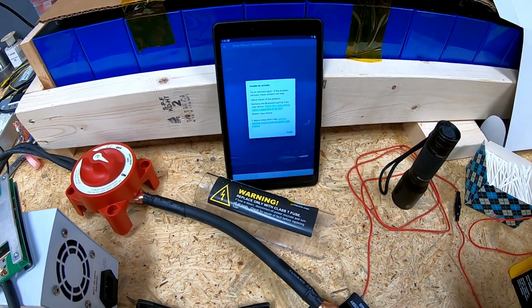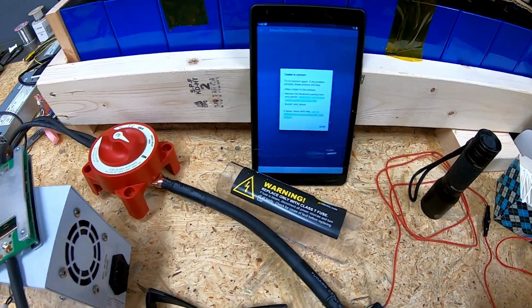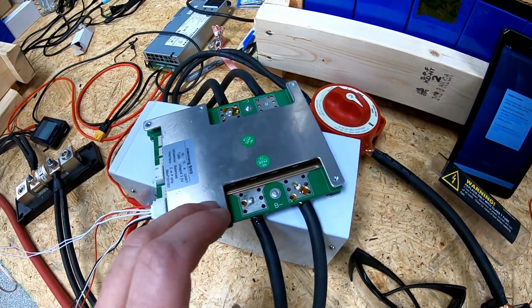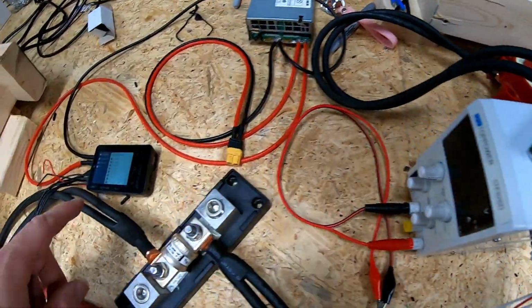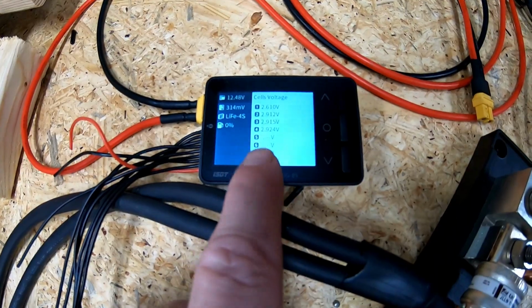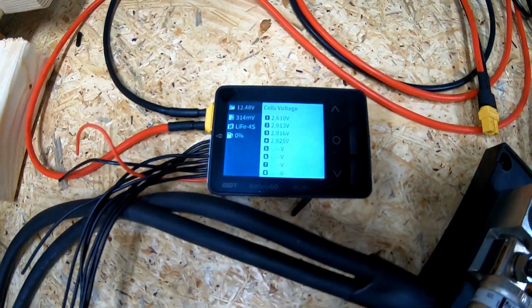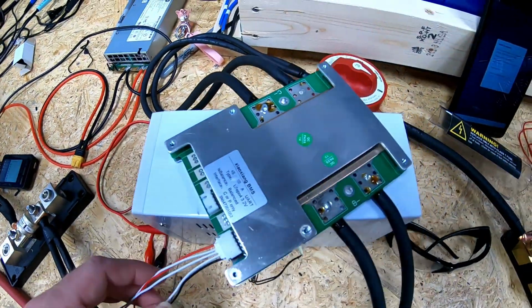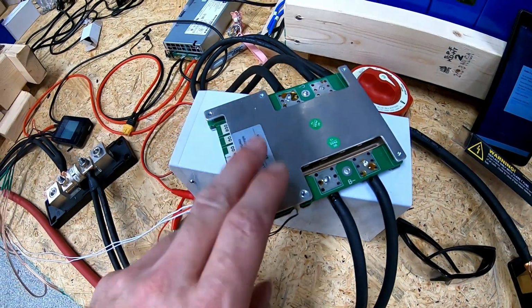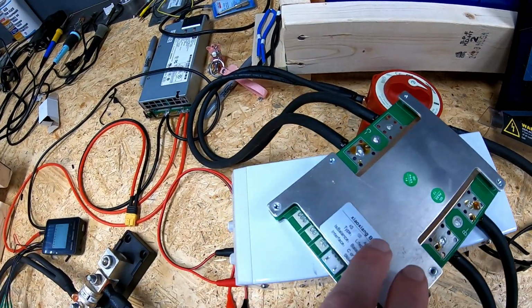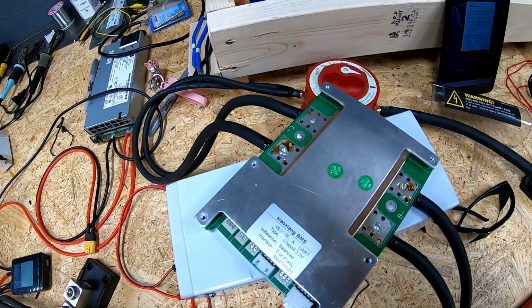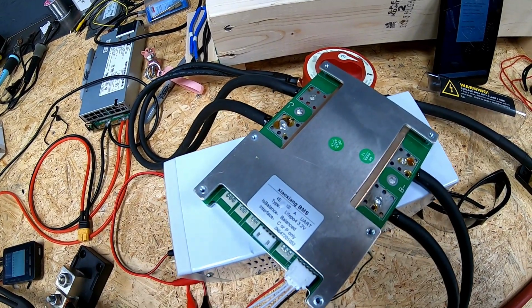Now, since the BMS shut down, more than likely it shut down when we hit that 2.5 volt mark on that cell, which I would expect. So that tells us the BMS did its job, killed the pack when that first cell dropped below where it should have been dropped for a safety margin.